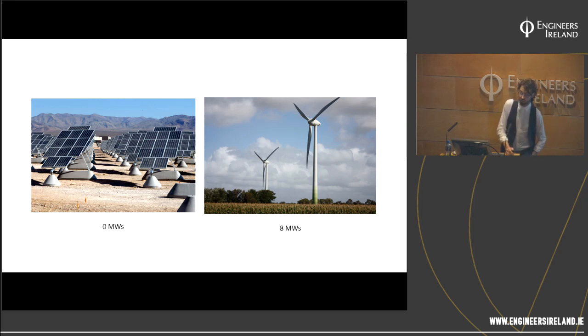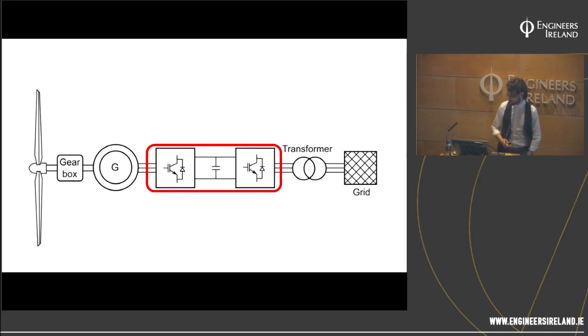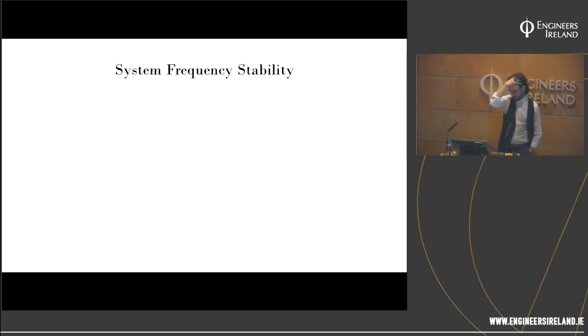Wind turbines are generally not synchronously connected to the system. They're non-synchronously connected, which means that it's electrically connected to the power system through power electronic devices. The reason manufacturers do this is because the wind speed is variable. So in order to harness the most amount of energy from the wind when the wind is moving, the machine will change its rotational speed to match the wind and harvest as much energy as possible. So this is the culprit, I suppose. That red box there is your power converter that decouples the speed of the generator from the grid frequency. So, okay, if you're believing me so far, synchronous inertia from the new sources is less than before.